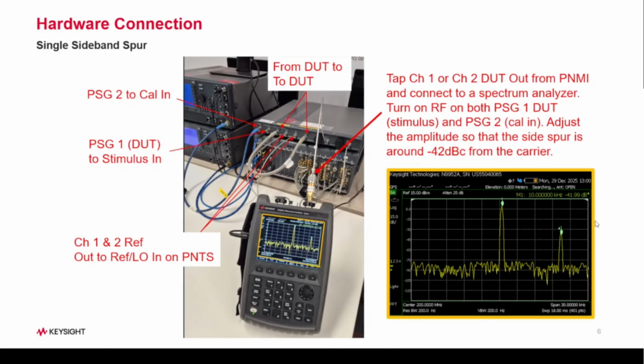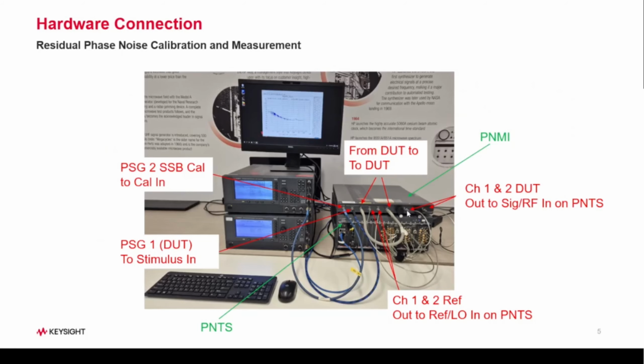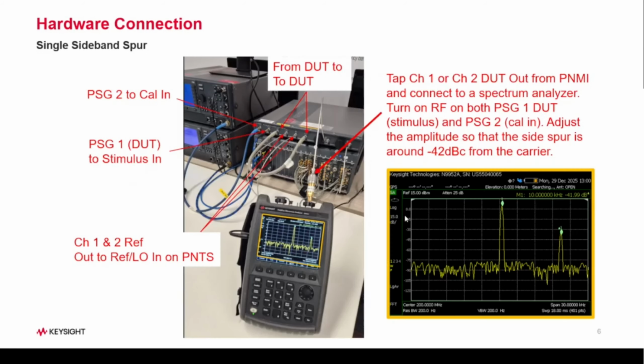Now, before we can run the measurement, you will have to run a calibration using the single sideband spur. We will look into how we set this up in the user interface in the next bit, but just to highlight what we have here from the previous slide, you would tap off the channel DUT out port. So the ports here, instead of having them connected to the RF port of the PNTS, you would take either one. So you can take either channel 1 or channel 2 and connect it to a spectrum analyzer.